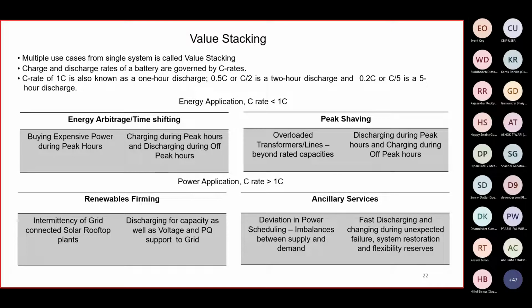And a particular energy storage is defined by its C rate, and the C rate is nothing but the charge and the discharge rate of a battery. So for example, a 1C battery is a 1 hour discharge, and similarly 0.5C or C by 2 is a 2-hour discharge. So mostly you will see that for energy applications, where peak shaving or the overloading of a line or an asset, say a transformer, happens for more than 1 hour, or say 2 hours in a day, that comes under energy applications, because the C rate is less than 1C.